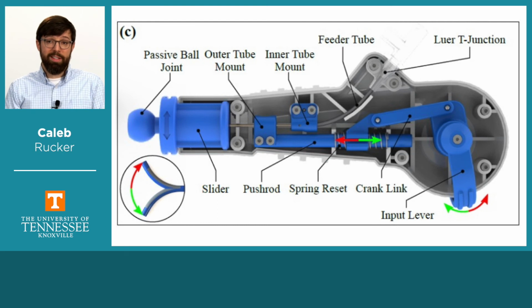This is what it looks like inside. You can see there's a simple lever mechanism that provides control of the tube translations, which then steers the tool at the tip. Lasers or baskets can be inserted down through a feeder tube, and the entire handle couples to the endoscope with a ball joint that allows the handle to be repositioned for ease of use.